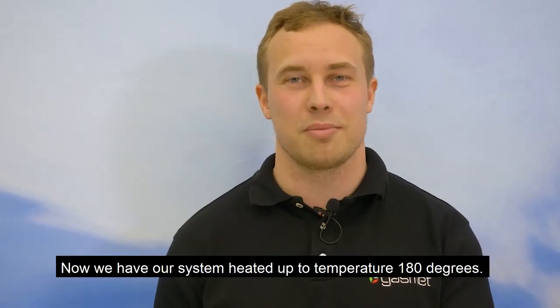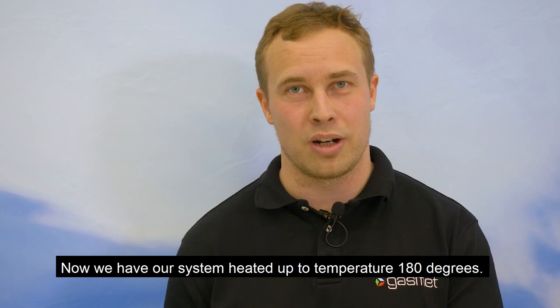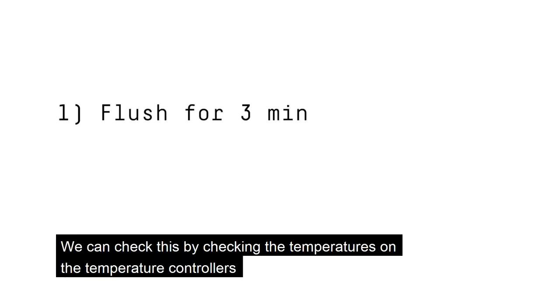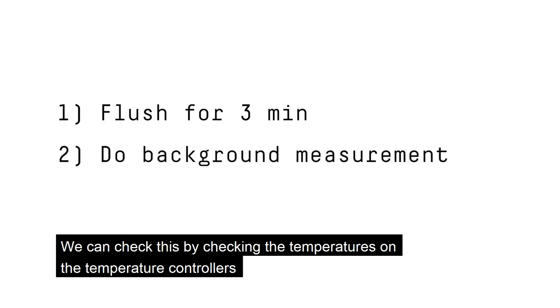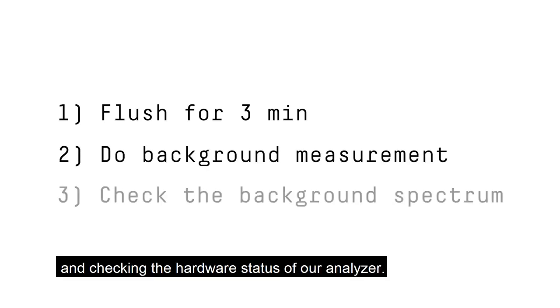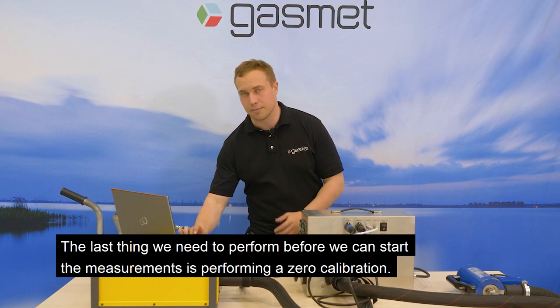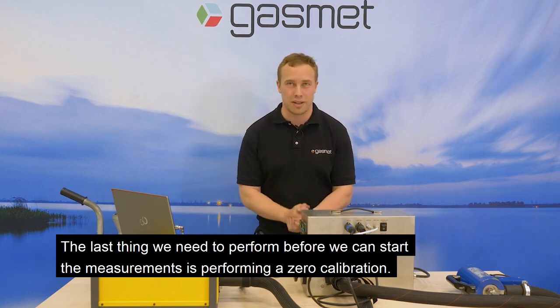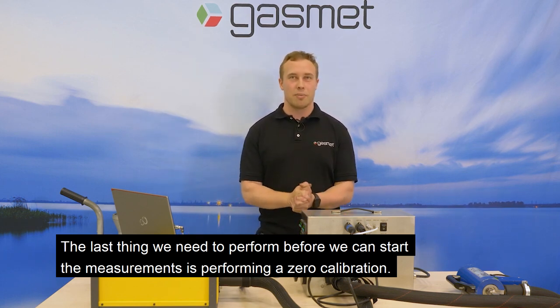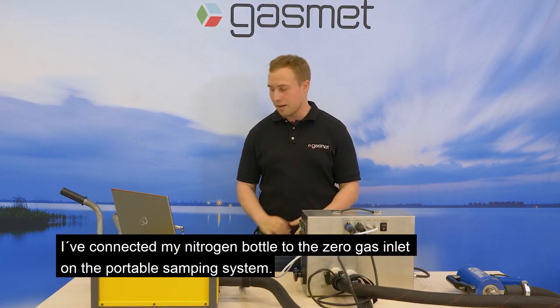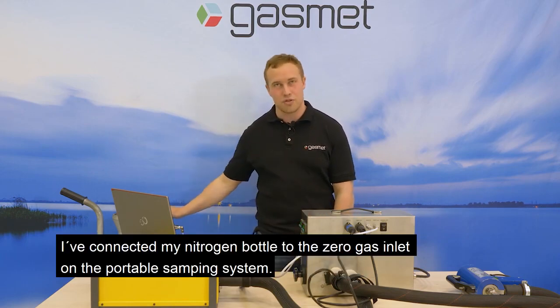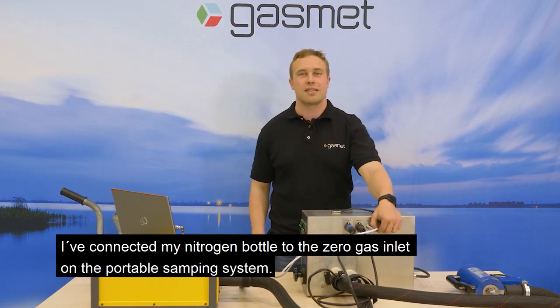Now we have our system heated up to temperature 180 degrees. We can check this by checking the temperatures on the temperature controllers and checking the hardware status of our analyzer. The last thing we need to perform before we can start the measurements is performing a zero calibration. And I've connected my nitrogen bottle to the zero gas inlet on the portable sampling system.